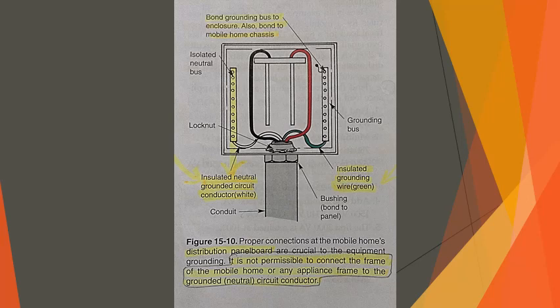Note particularly that the neutral conductor is completely insulated and isolated from the grounding conductor, as well as the equipment enclosure. In addition, the mobile home chassis must be securely bonded to the grounding bus or grounding conductor, as must all metal, non-current carrying equipment inside of the mobile home. This grounding continuity is essential and will be checked by the inspector.